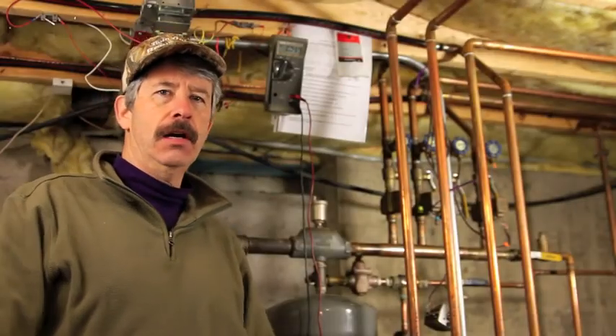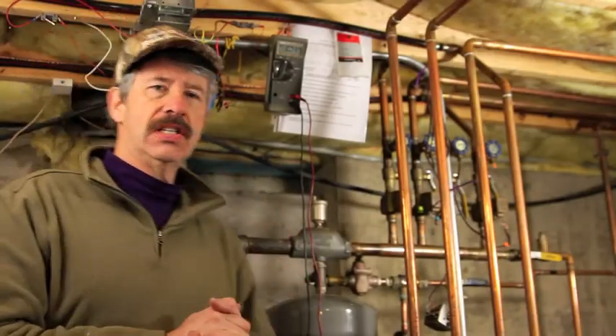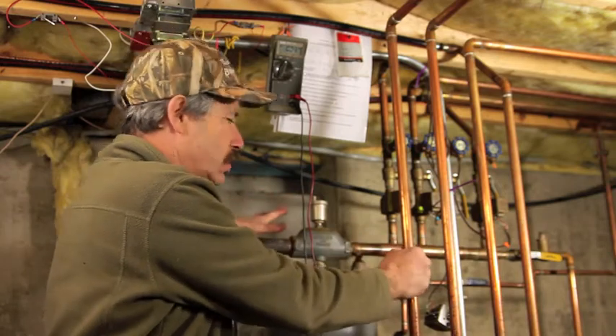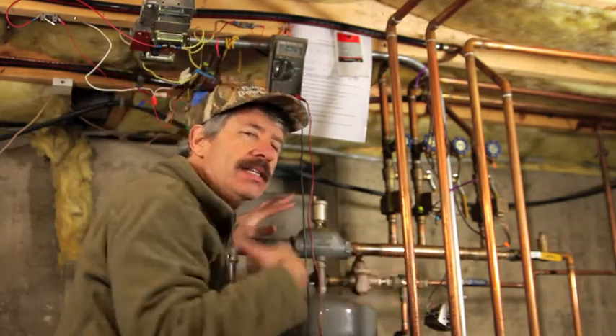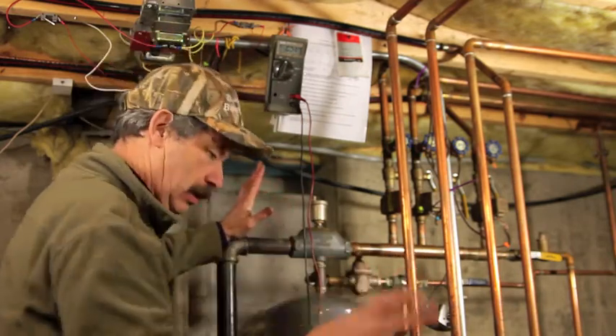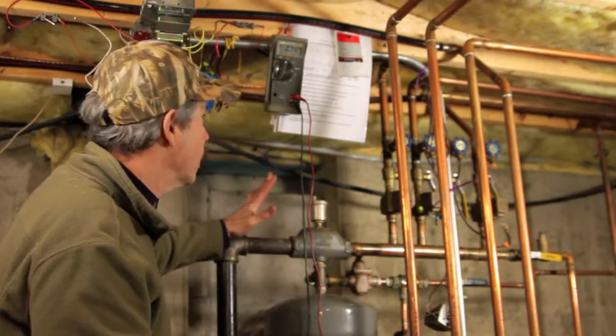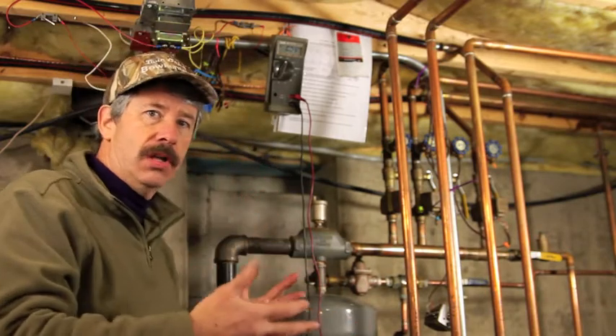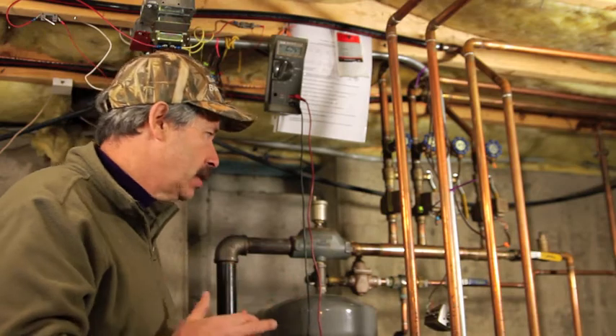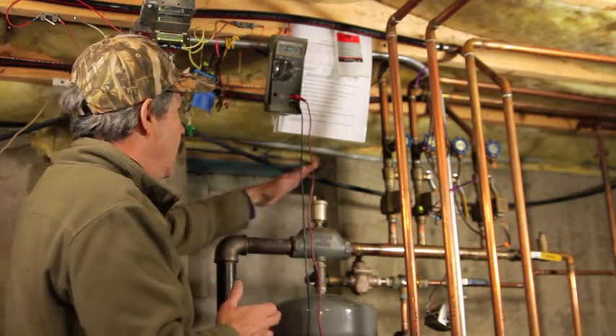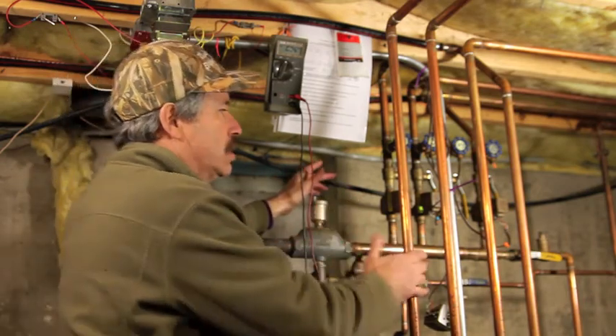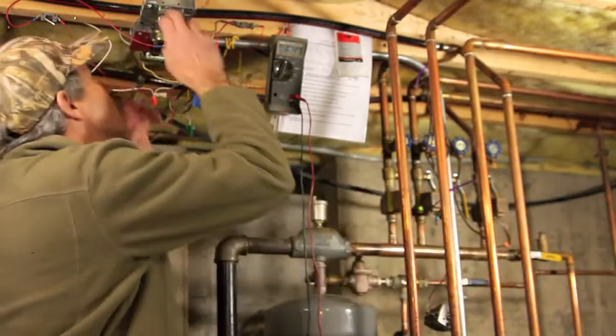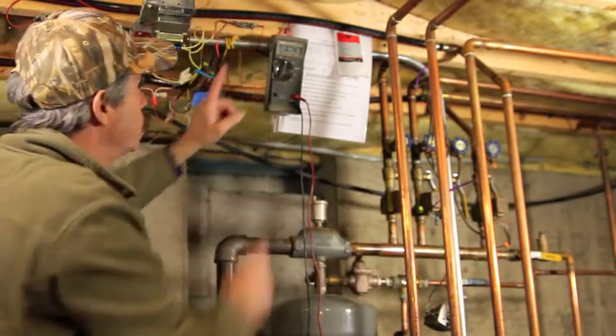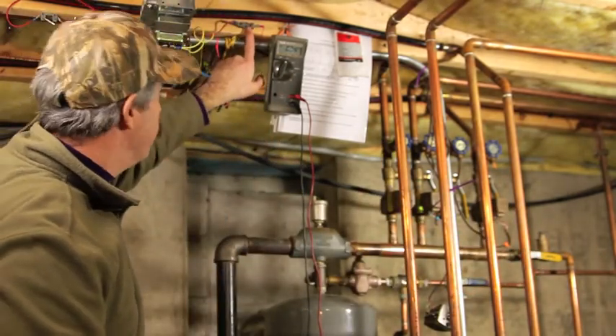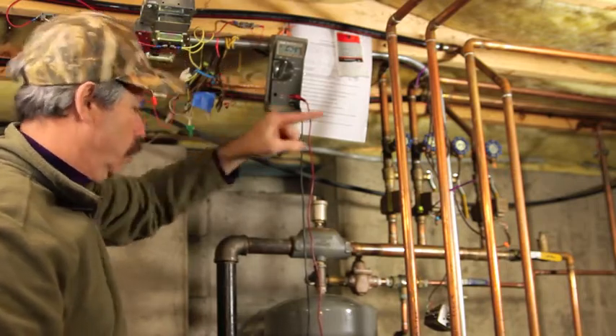Wannabe farmer here, showing you how our heating control system is set up for my family in case they want to go check this out, or I'm not here and they need to do some troubleshooting, or somebody else comes along and needs to know how our system works. Our system has 4 zones, 2 transformers. Each transformer is fused and going to 2 of the zones.